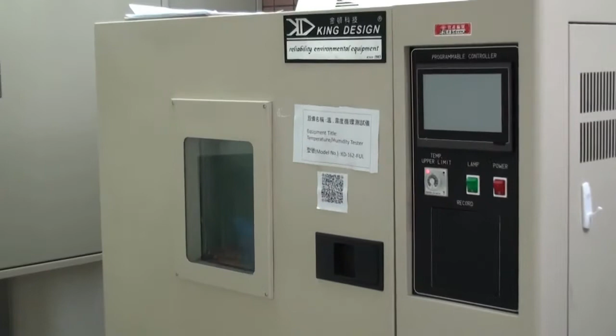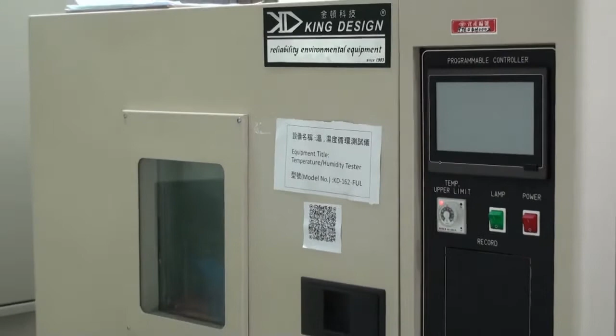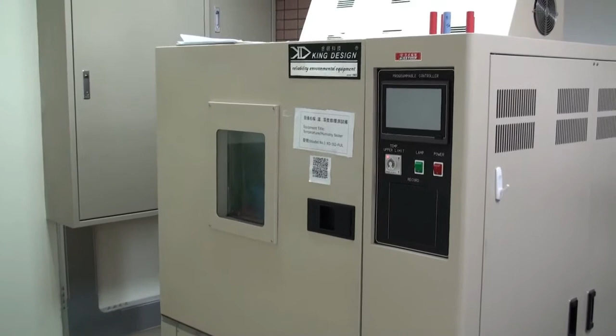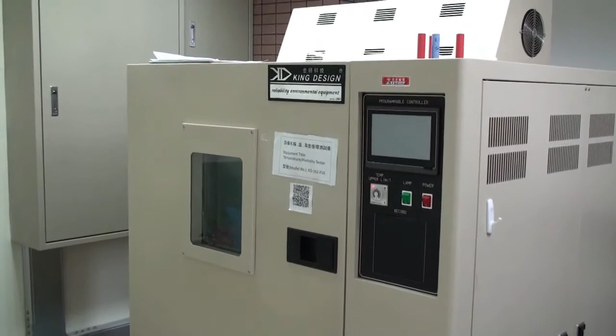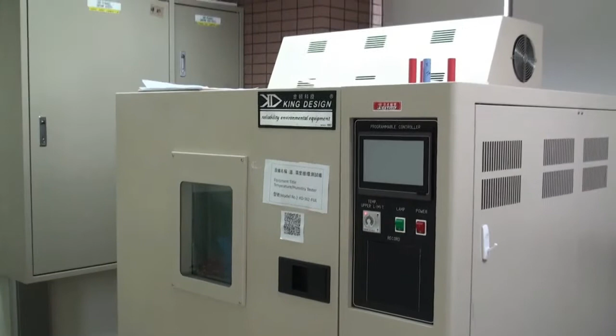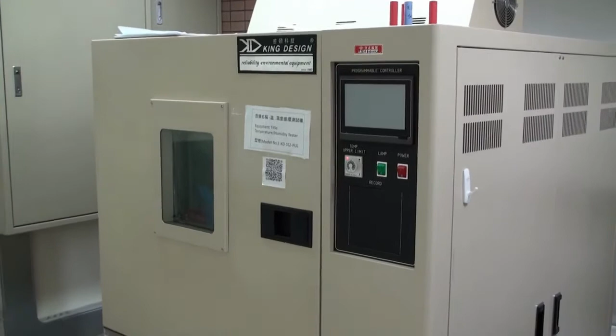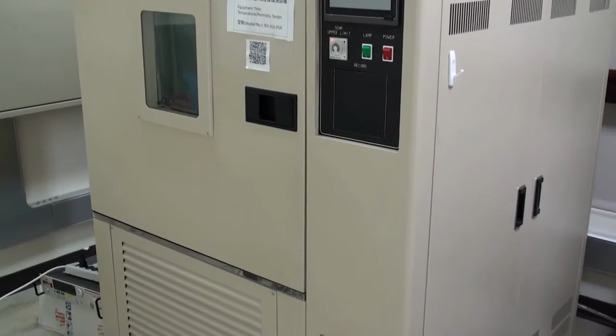This is a temperature and humidity controller from King Design, model number KD162FUL. We use it for acceleration tests to check product reliability. The temperature range is minus 70 degrees Celsius to 190 degrees Celsius. It has a cooling capacity from 85 degrees Celsius to minus 40 degrees Celsius in 20 minutes, and a heating capacity of 24 degrees Celsius to 190 degrees Celsius in 30 minutes. The relative humidity range is 20% to 98%. It has two modes, fixed mode and programmable mode. In programmable mode, we can change the input parameters of temperature and humidity with specific timing.